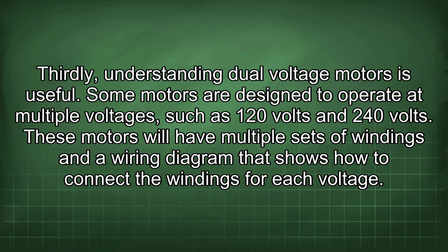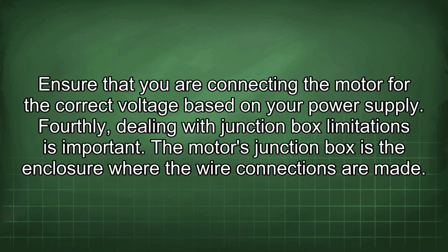Thirdly, understanding dual voltage motors is useful. Some motors are designed to operate at multiple voltages, such as 120 volts and 240 volts. These motors will have multiple sets of windings and a wiring diagram that shows how to connect the windings for each voltage. Ensure that you are connecting the motor for the correct voltage based on your power supply.